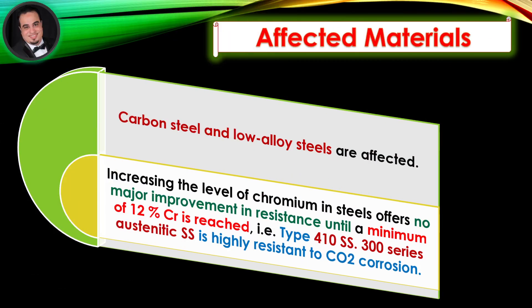Affected materials: Carbon steel and low alloy steels are affected. Increasing the level of chromium in steels offers no major improvement in resistance until a minimum of 12% Cr is reached. For example, type 410 stainless steel and 300 series austenitic stainless steel are highly resistant to CO2 corrosion.